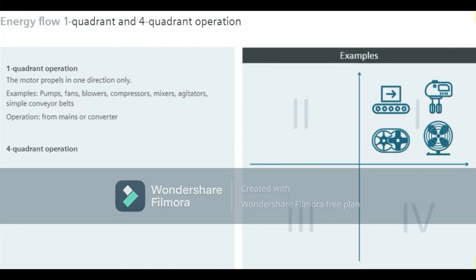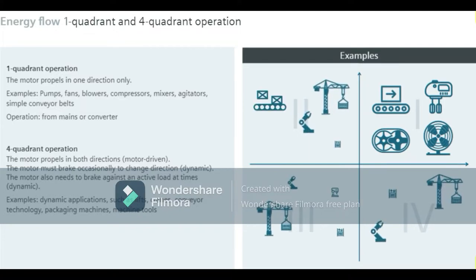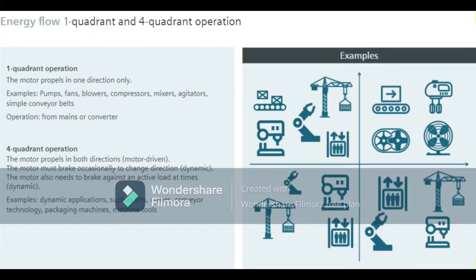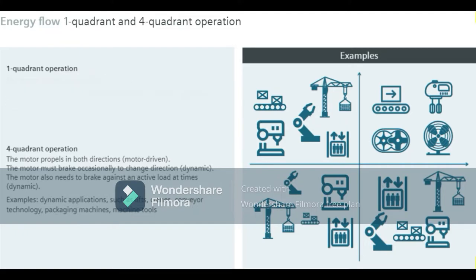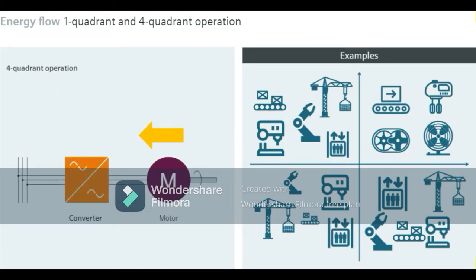In four-quadrant operation, the motor switches directions in motor-driven mode and sometimes operates dynamically. Examples of such operation are most dynamic applications such as lifts, cranes, converter technology, packaging machines, machine tools, and many more. These requirements are almost always met with converters. However, electric energy flows back into the converter during dynamic operation, and the intermediate circuit capacitor can only absorb energy to a certain extent. You will learn how to overcome such circumstances on the next few slides.